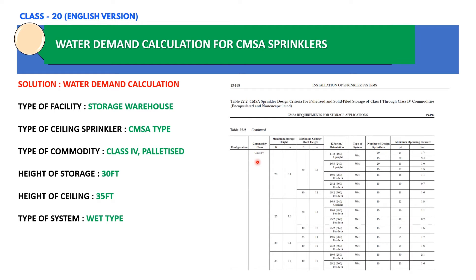I have extracted the table for class 4 commodity, which shows maximum storage height in feet and meters. Based on a storage height of 30 feet — which is 9.1 meters — and a maximum ceiling height of 35 feet, we can identify the appropriate row. Based on this, we select a pendent type sprinkler with a K factor of 19.6. Since the system is a wet system, the number of sprinklers to be considered for our area of operation will be 15, and the minimum pressure required for each sprinkler will be 25 PSI or 1.7 bar.